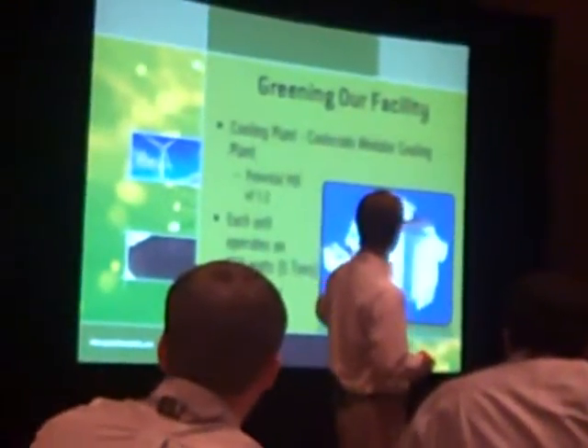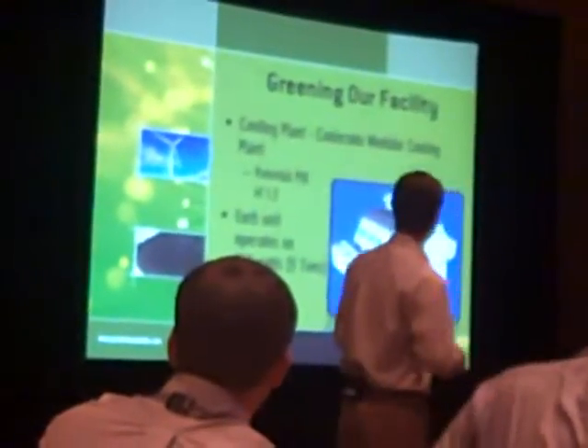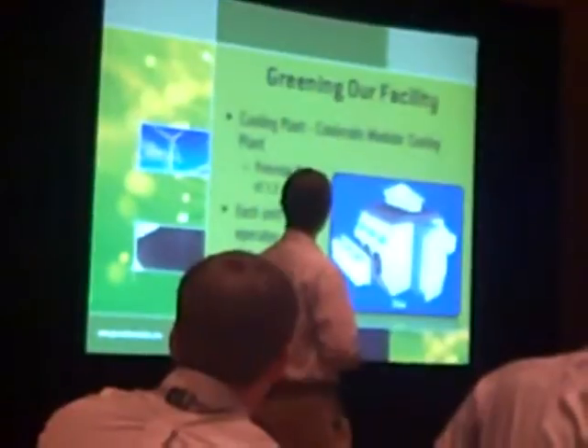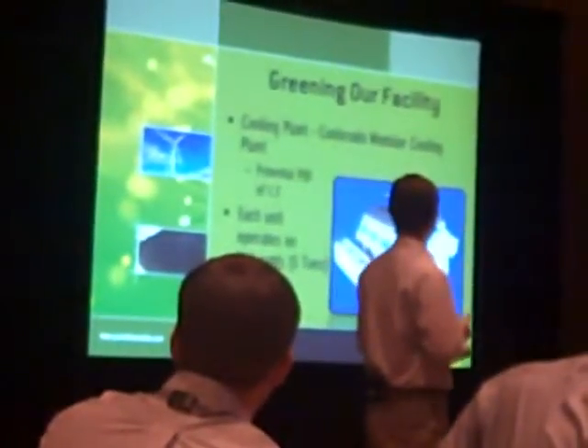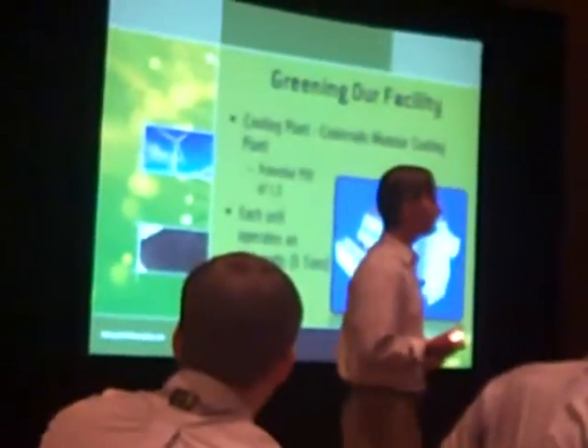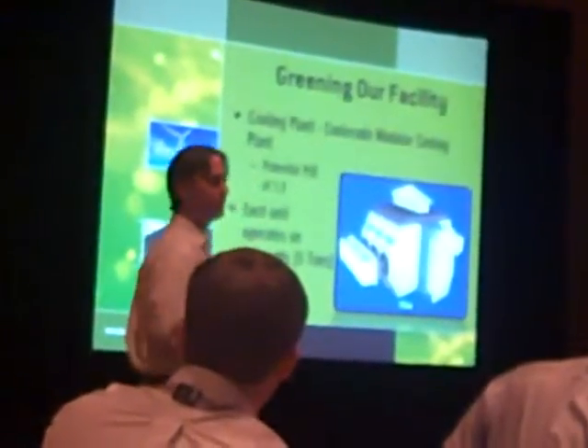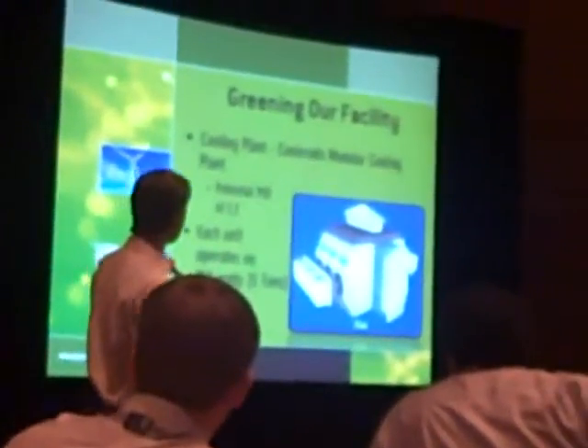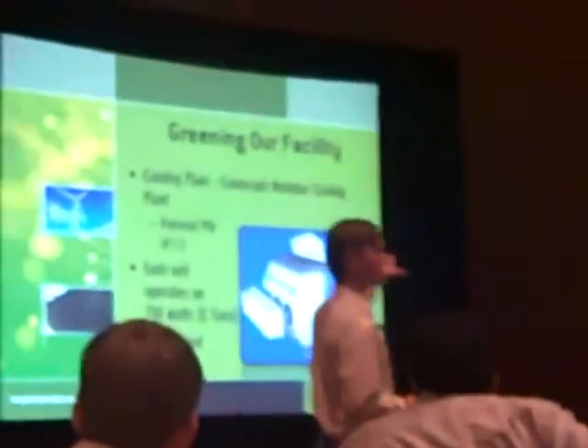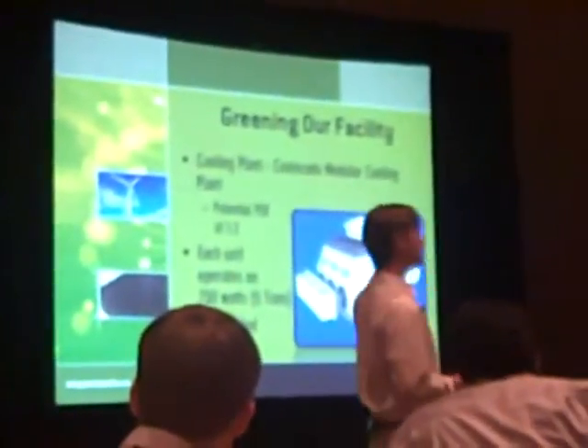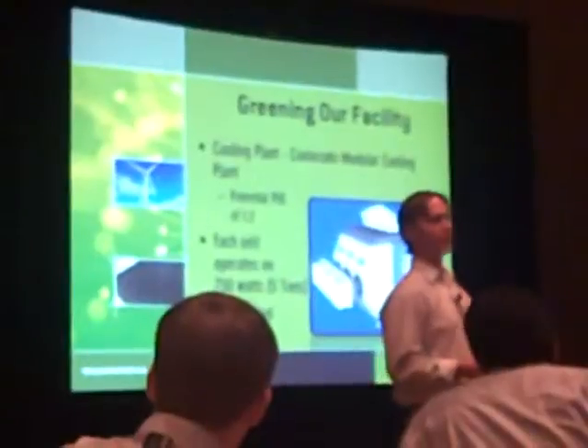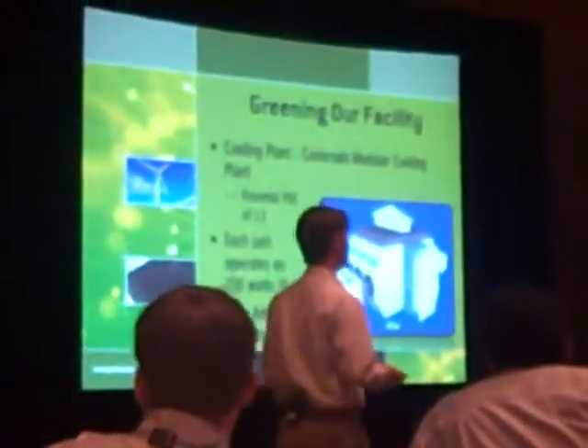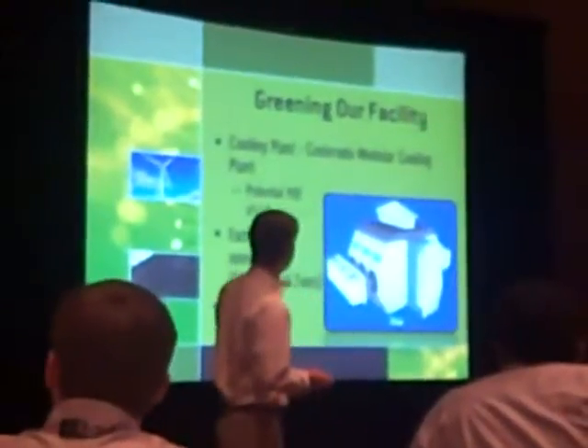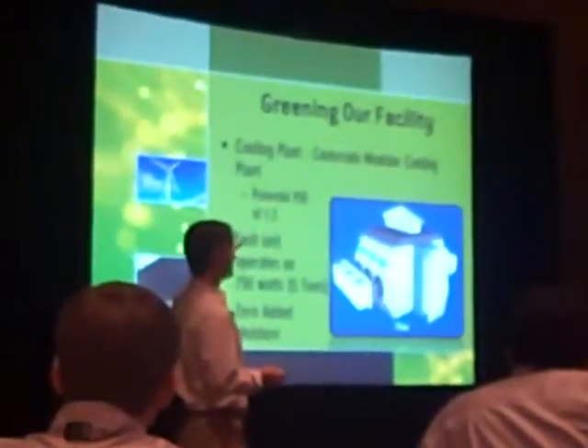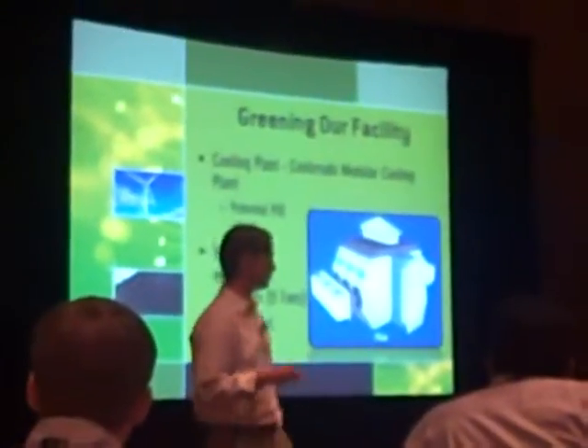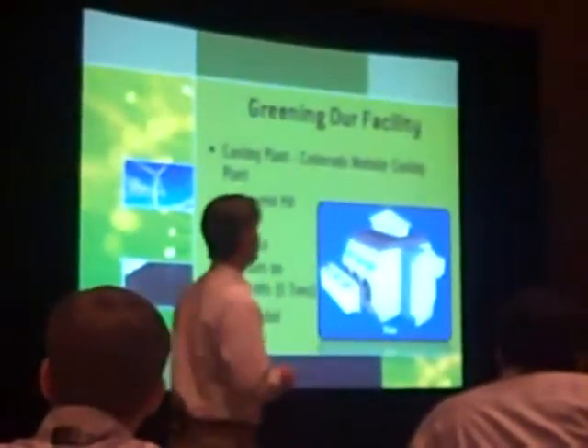It can actually deliver us a PUE of about 1.2 into the data center using forced air. Each unit operates on about 750 watts of energy. So I think you will recognize that's an incredibly small amount of cost on an operating basis. Most importantly, what it does for us in Cheyenne, if you recall a couple slides back, our relative humidity does not add any moisture into our facilities. The traditional economizer utilizes an evaporative cooling technique. This uses a technique, but then exhausts the moist air back into the atmosphere before it comes into the data center and passes through the exact same moisture content as the outside air.